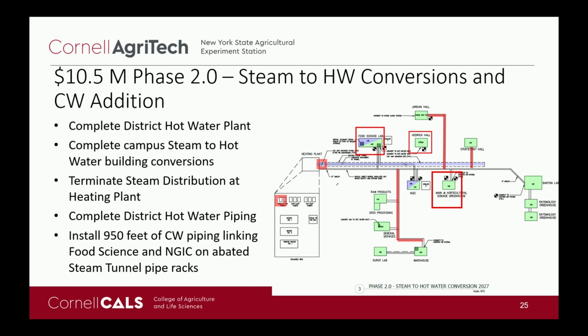So the plan is to reuse the steam tunnel for that purpose, highlighted on the sketch as the blue line. It's the first step toward our distribution for chilled water. We would dispatch chilled water more efficiently, utilizing the two machines proposed to be installed around the same time through the parallel projects.